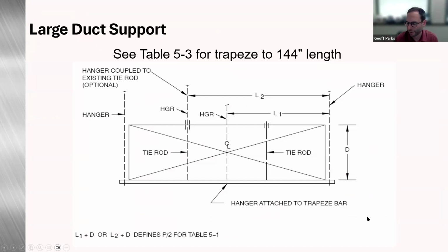So what I really wanted to get to with large ductwork is the large duct supports. I just wanted to highlight the construction really quick. So this is figure 5-7 on page 5.15 out of the duct construction standards. Basically, table 5-3, to size your trapeze, only goes up to 144 inches in length. So when you are beyond that with large duct, you either have to go to the rectangular industrial to size your hangers, which I'll also show later on.